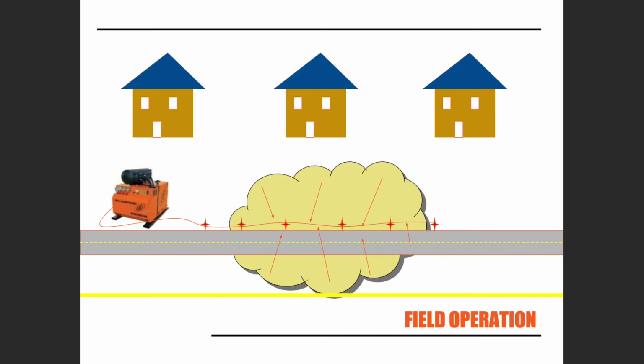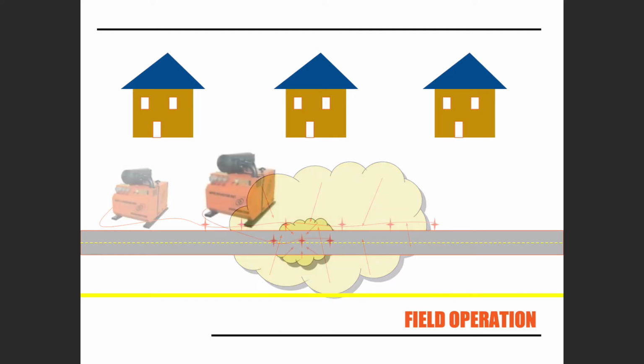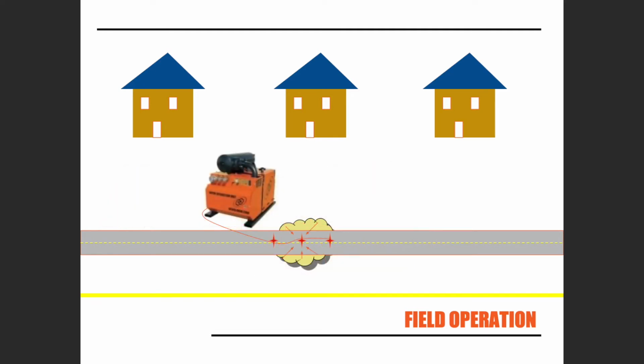Probe 1 and Probe 6 are now zeroed out, and you are starting to see the accurate pinpointing process take place. Look at that, the plume of gas has been vacuumed out, and the leak is now found. It is on probe number 2 in the series of 6 probes. Please note that this is just one of many different scenarios that can happen when out on a gas leak.